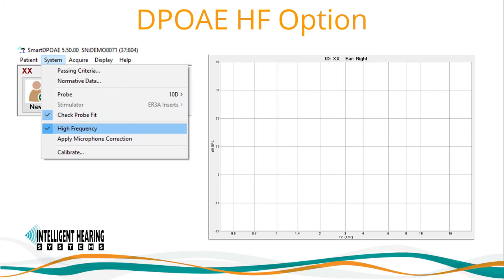The Smart DPoAE module offers a high-frequency option for clinical ototoxicity testing. When activated using the 10D probe, the DPgram frequency range will expand to 16 kHz. For researchers performing animal OAE testing, there are options to record responses to stimuli up to 32 kHz using a combination of a 10B-plus probe microphone and special animal-use-only high-frequency transducers.